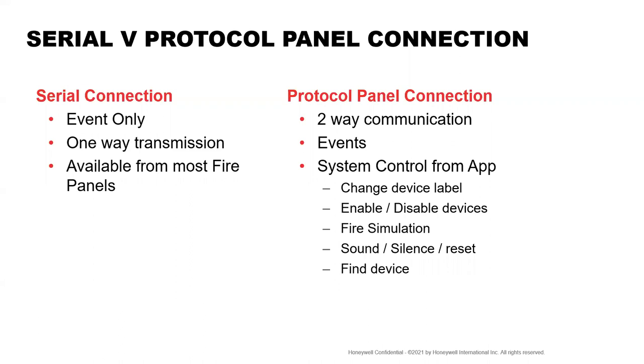Also, from the phones and from your remote systems, you can sound the alarms. You can silence the alarms if it's all in working order and whatever. You can stop the bells ringing, because that tends to make people panic. If indeed you find out that it's not a real fire and it has gone off by accident, you can actually reset it remotely now. This was the thing that used to scare the life out of people, because they didn't want people doing that remotely. It's not quite as easy as just looking up at your phone, hitting the reset button, and it all stops. But there is a level of control.